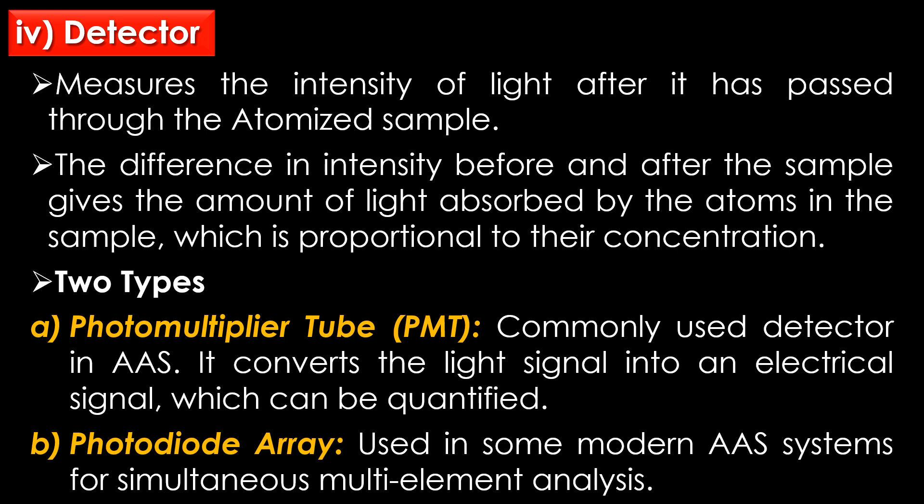The fourth part is the detector, which measures the intensity of light after it has passed through the atomized sample. The difference in intensity before and after the sample gives the amount of light absorbed by the atoms, which is proportional to their concentration. There are two types of detectors: the photomultiplier tube and the photodiode array. The photomultiplier tube is the most commonly used detector; it converts the light signal into an electrical signal which can be quantified. The photodiode array is used in some modern AAS systems for simultaneous multi-elemental analysis.